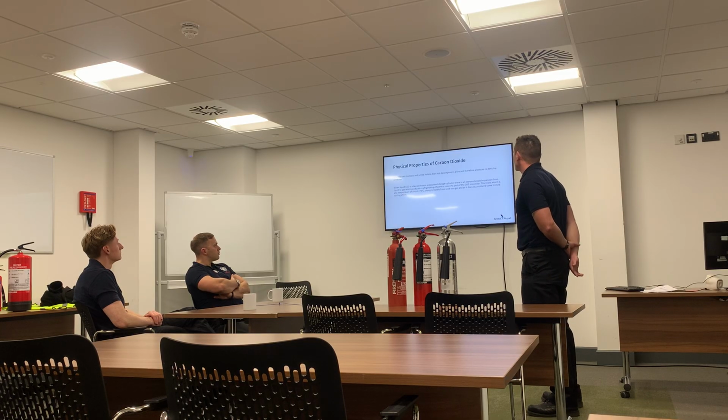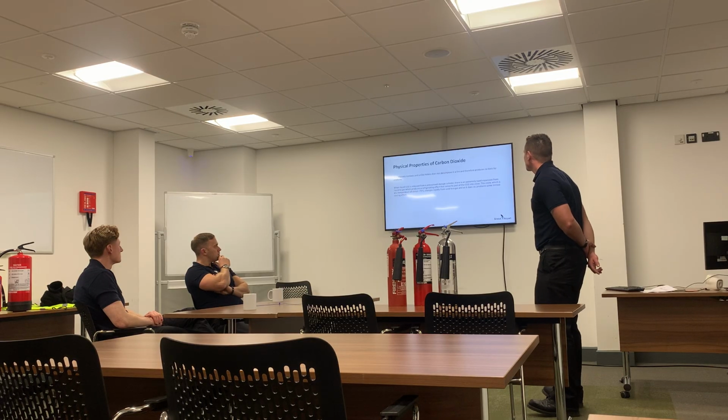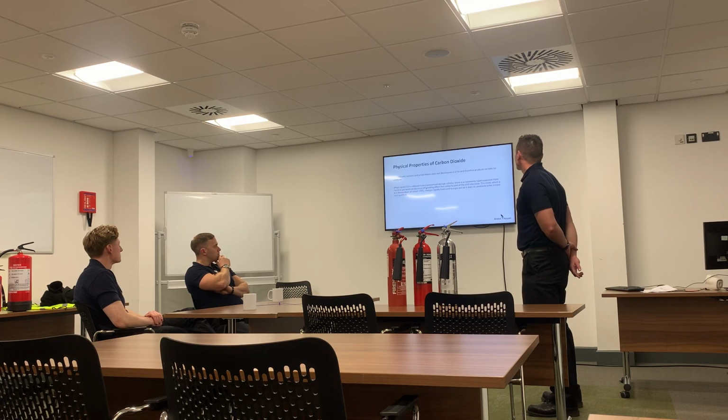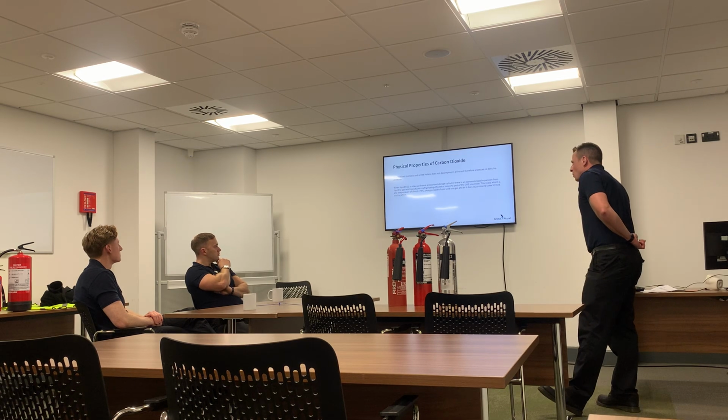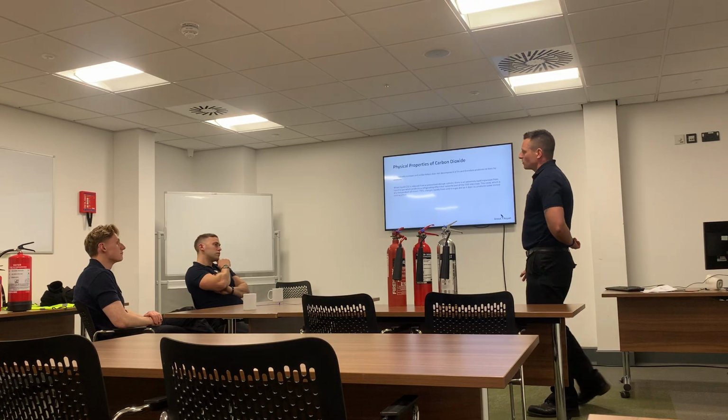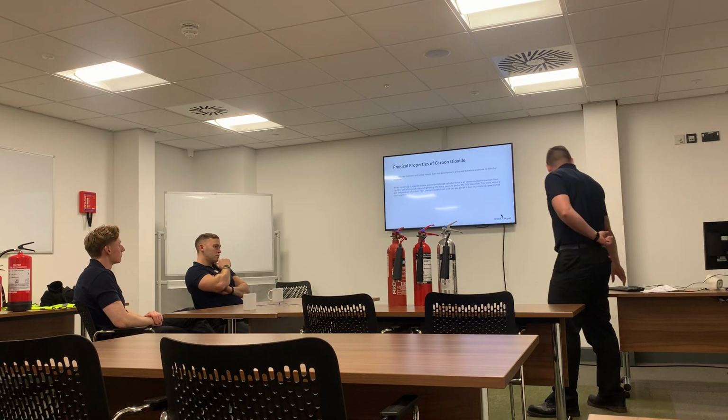When liquid CO2 is released from a pressurized storage cylinder, there is an extremely rapid expansion from liquid to gas, which produces a refrigerating effect that converts part of the CO2 into snow. This snow, which is at a temperature of about -79°C, changes rapidly from solid to a gas, and as it does so, produces some limited cooling effect. It's important to know that there's not a great deal of cooling effect with CO2.